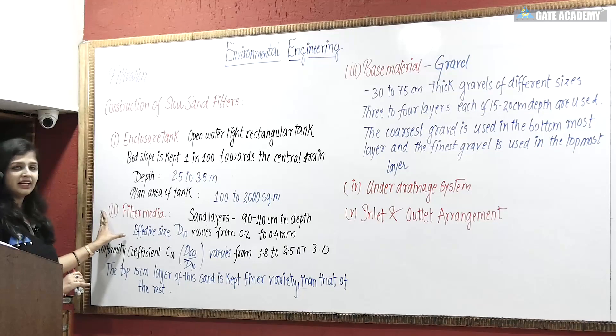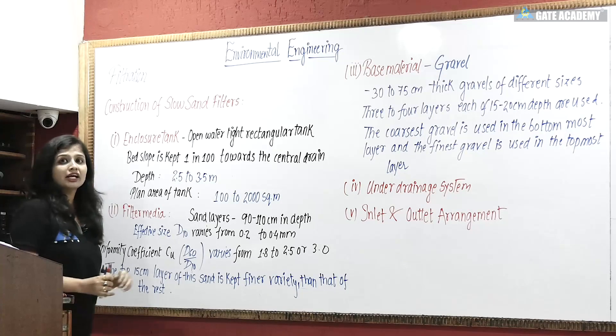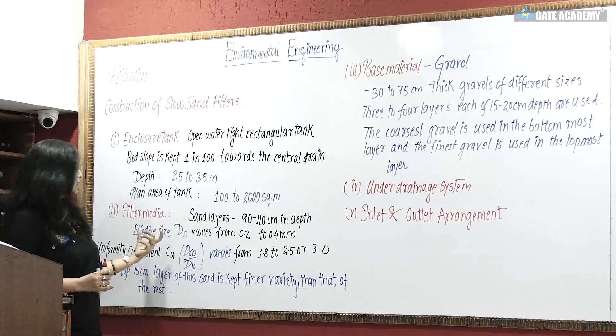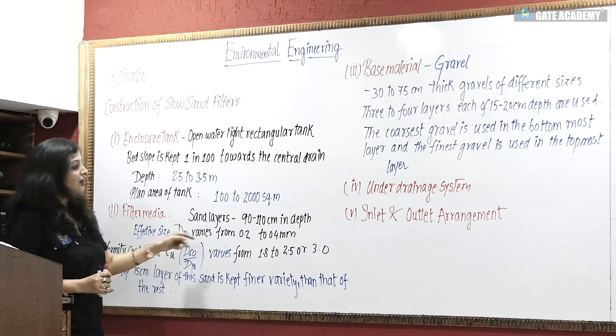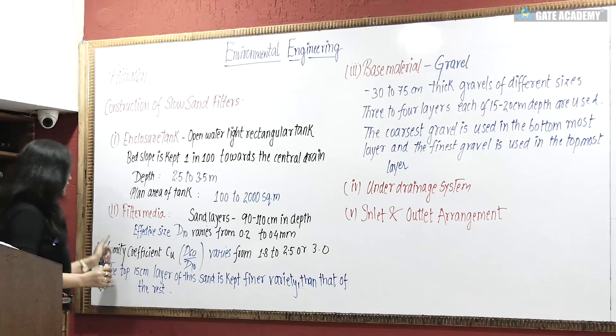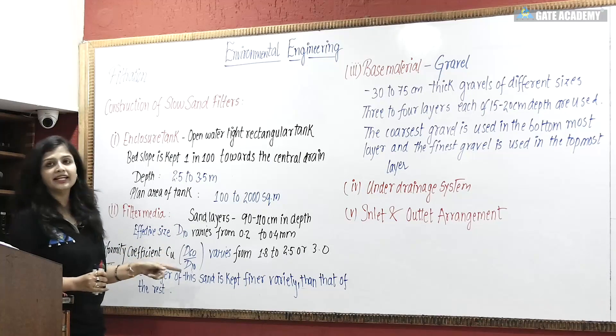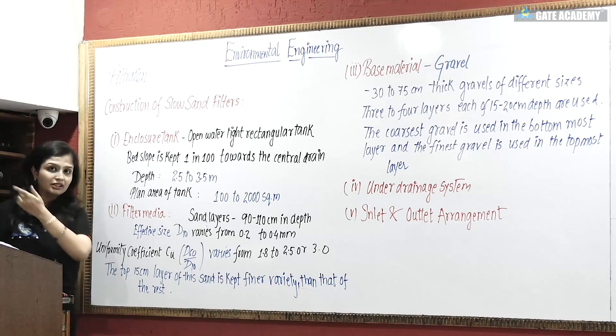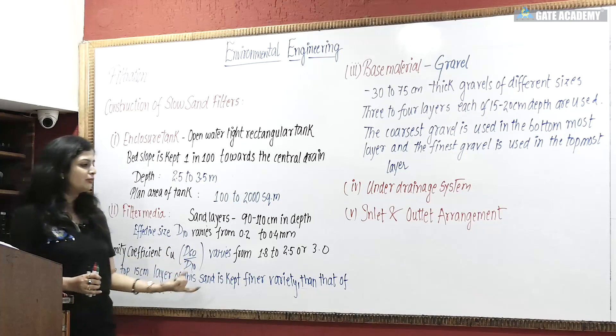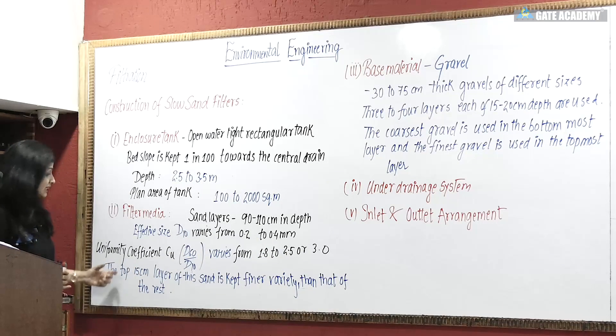For the filter media: the sand layer depth is 90 to 110 cm. The effective size D10 varies from 0.2 to 0.4 mm. You have to know this because the value of effective size and the uniformity coefficient will vary when you talk about rapid sand gravity filters. Here the uniformity coefficient CU, which is D60 upon D10, varies from 1.8 to 2.5 or up to 3.0.